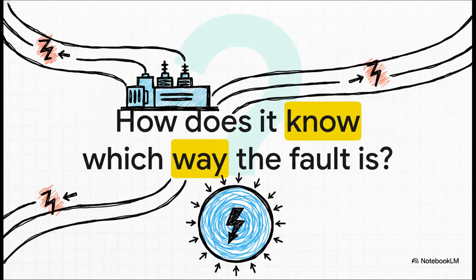Wait a second. This plain circle has no direction, so how does it actually know which way the fault is? Think about this. If the relay is sitting at a substation, a fault could happen on the line directly in front of it or on a completely different line right behind it. Because the circle expands equally in all directions around the origin, this plain impedance relay is completely blind to direction. It might accidentally trip your power line for a problem happening miles away in the exact opposite direction. Not great. But watch how the solution evolved.